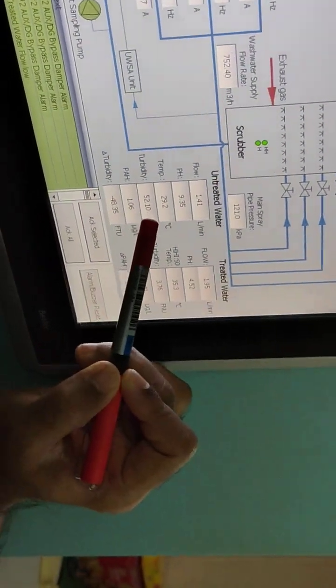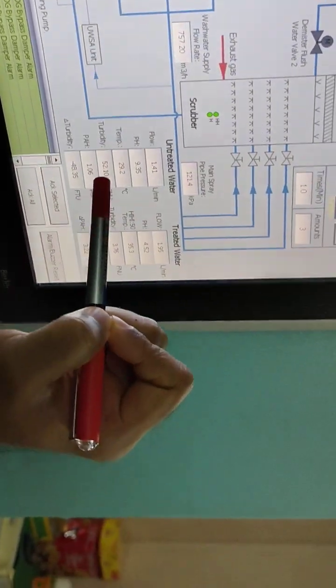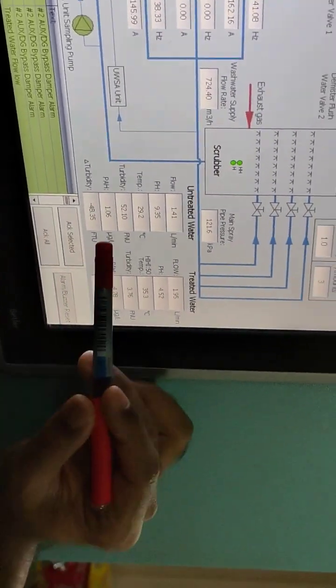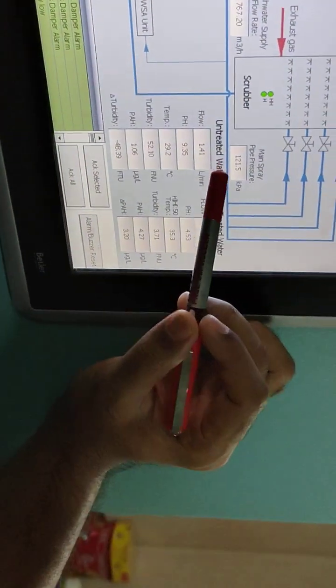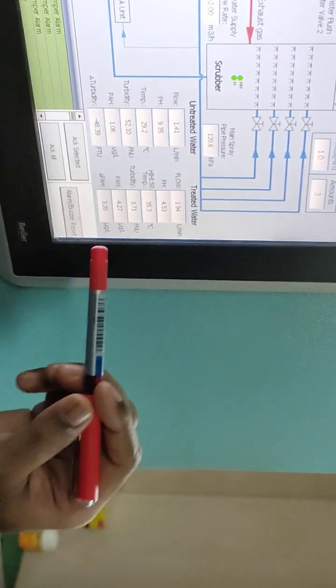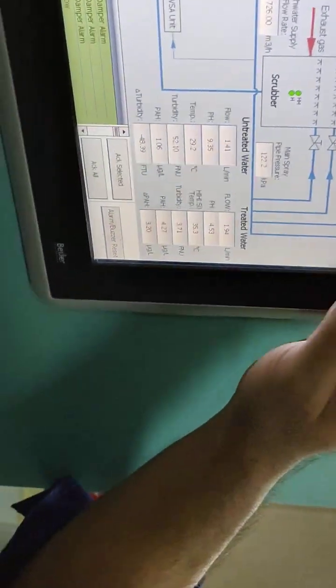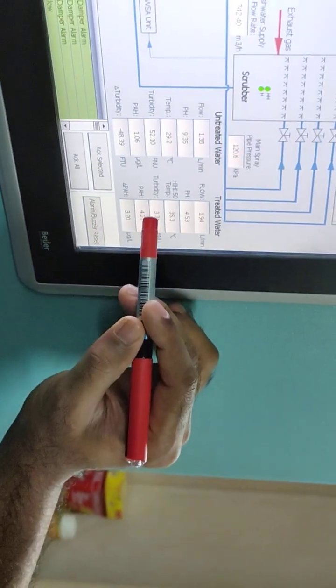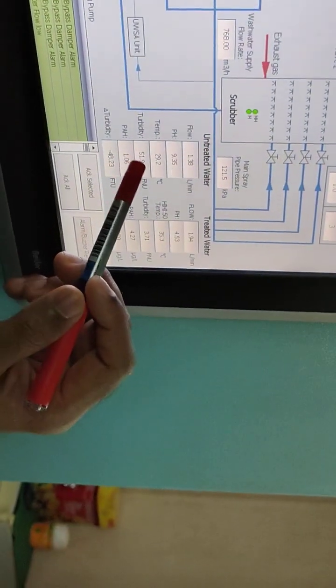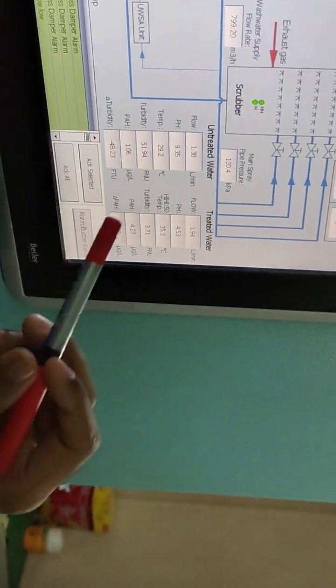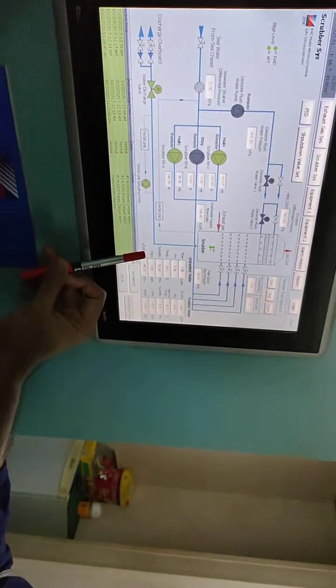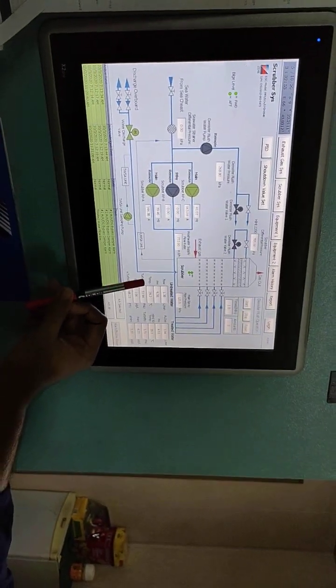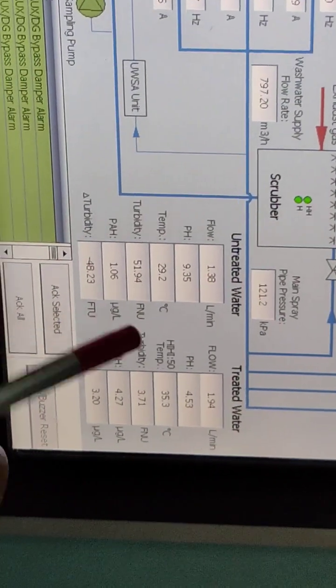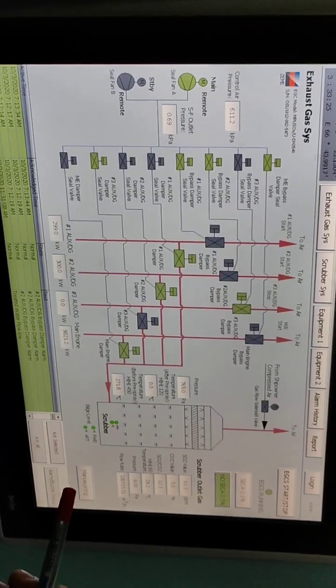This turbidity sensor we have already explained to the office as well as to the technician. This time when they come for servicing this PLC, you have to explain it to him. Last time when the technician came, we actually took a treated water sample and an untreated water sample and checked visually which water is dirty. The treated water is dirty actually, because it has rust and all the other items from here. So this water is supposed to be more turbid than the inlet water. But this sensor is working, but some deviation is there. You need to calibrate it to zero. Calibration needs to be done for this one. Then pH is okay. Delta turbidity is directly compared to this turbidity, so once this value gets adjusted, automatically this one will also be okay. Stop. Clear? Sir. Okay, now the scrubber system is finished.